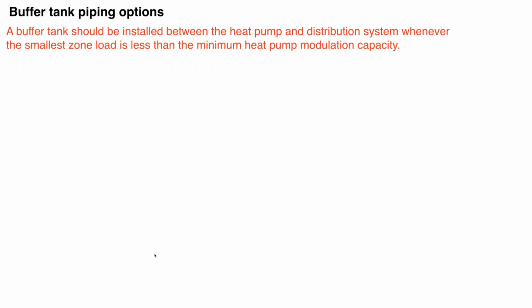Now, when we pipe the buffer tank, there are different ways to do it, all right? And what this says here: a buffer tank should be installed between the heat pump and the distribution system whenever the smallest zone load is less than the minimum heat pump modulation capacity. In theory, if we had any heat source, a heat pump or a boiler, that could modulate from 100% right down to literally zero, we would not need a buffer tank, because we could always adjust the heat output of that heat source to match what our distribution requirement is.